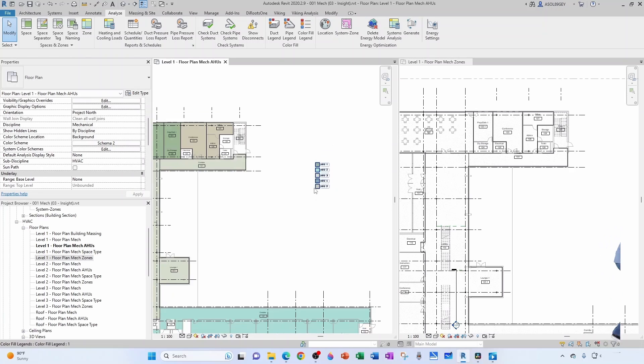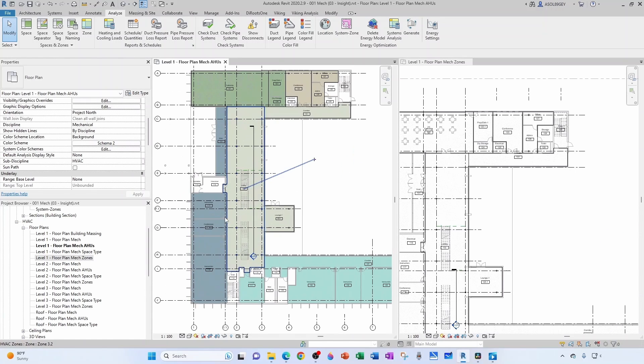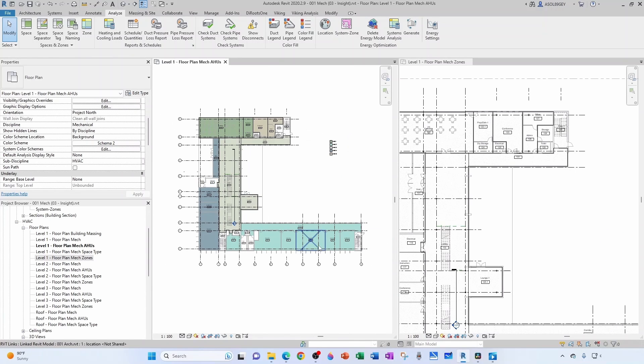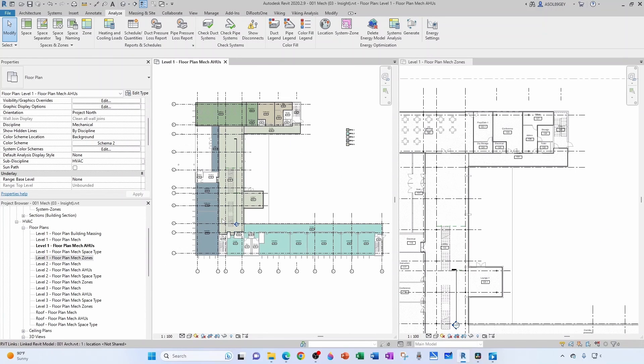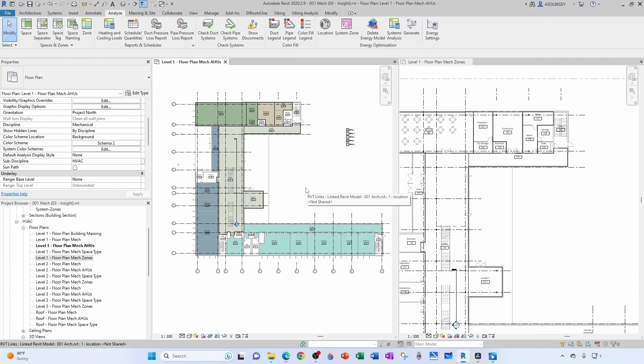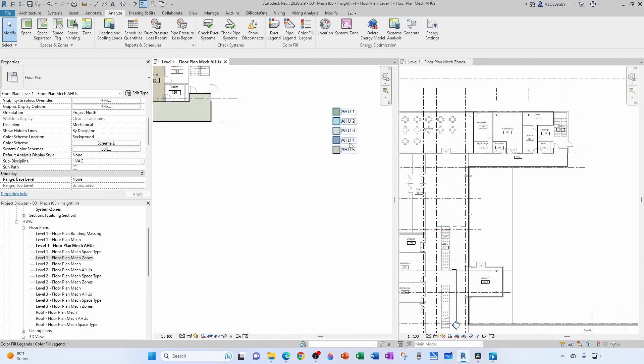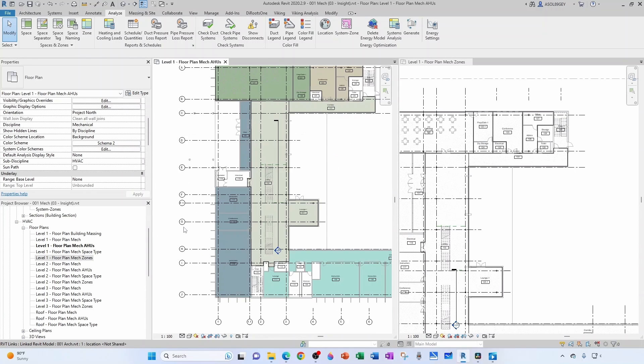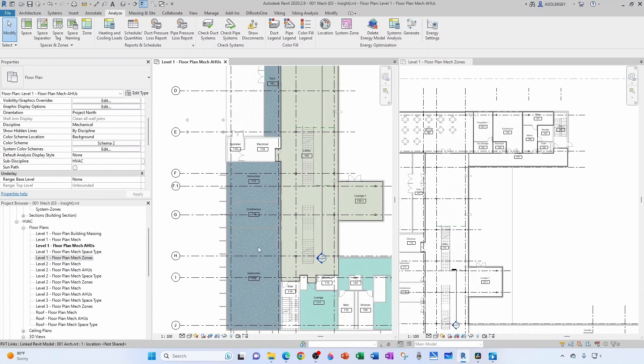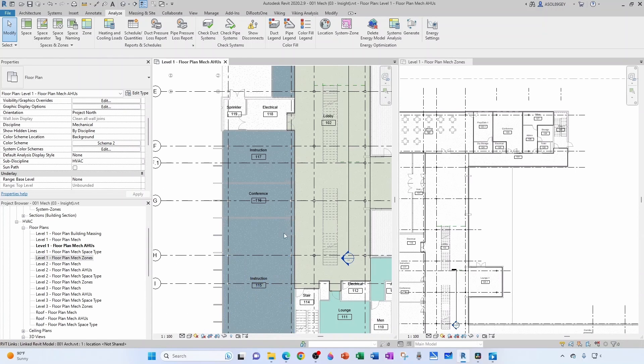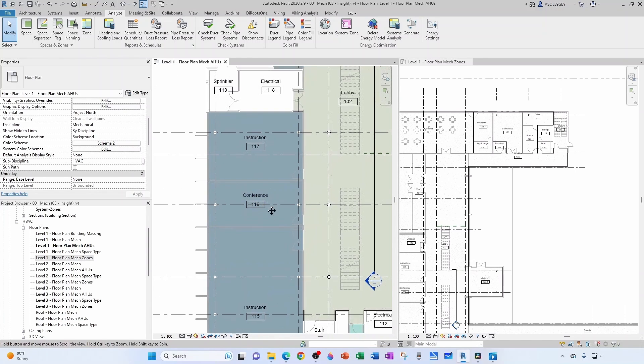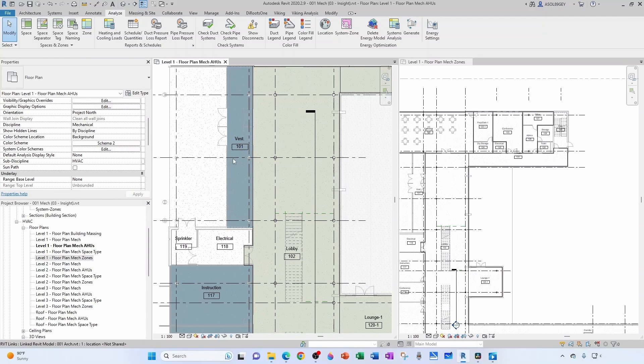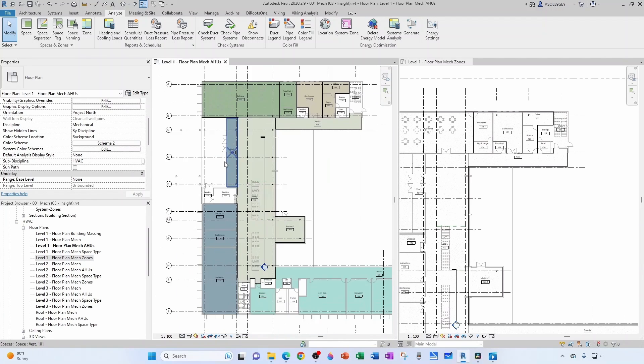Let's go with air handler 4, which is this one here. And sometimes you don't have this breakdown and you have to do your cooling loads first for all the spaces and then you start grouping into zones and then you start grouping into air handlers, or you start grouping into air handlers and then splitting into zones. It depends on your workflow and the information you have available. But for now I know that AHU4 is going to be serving all this, and I'm going to have this vestibule separate, conference separate, vestibule separate, and this vestibule separate.